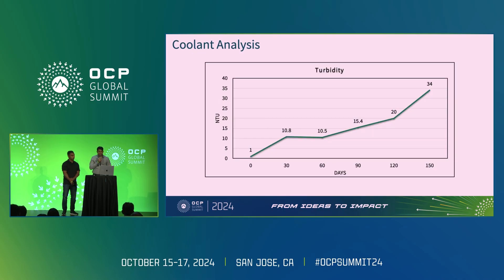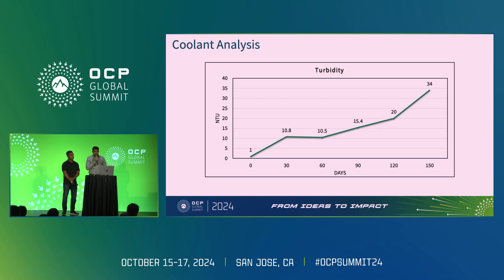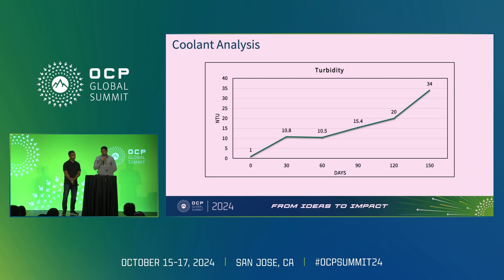On the turbidity analysis, at day zero the baseline sample had 1 NTU of turbidity on average. At the 150th day, the turbidity value increased to 34 NTU. We are further investigating the correlation of turbidity and how it would affect the coolant's performance and how it correlates with the erosion mechanism. We are still in an experimental phase of that.